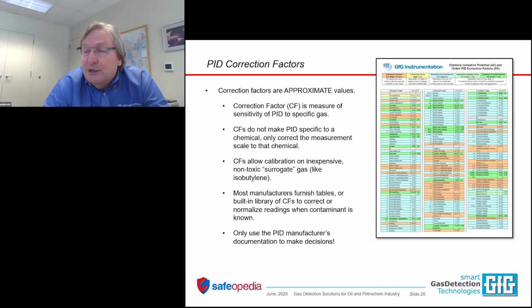But there's one limitation to this approach. Correction factors are approximations. They're pretty good, but they're still approximations. And they can change a little bit over the life of the sensor or as a function of ambient environmental conditions, like changes in humidity.